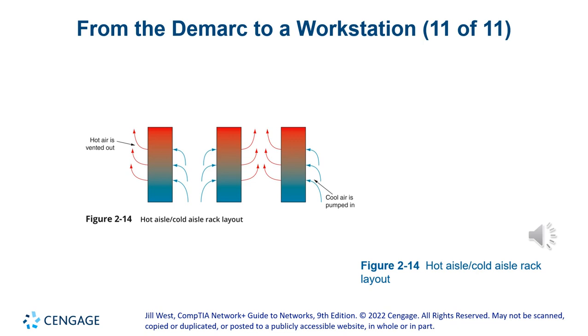Okay, it happened to us one time at Miami-Dade that we put three big routers, like three racks next to each other, and they were just side by side. And the cooling on that equipment was left to right, not front to back. So that's the problem that we had: the first one would suck in all the cold air, push it onto its left side as hot air, but then that's the intake for the other one. So this one was inhaling that hot air, heating it even more to cool itself, and then pushing it to the third one. So guess what? The third one was getting all the heat.